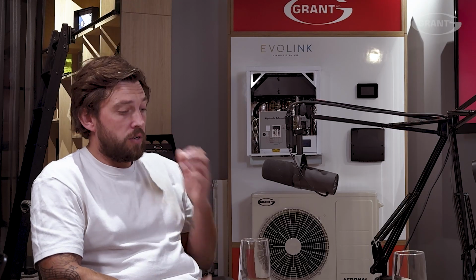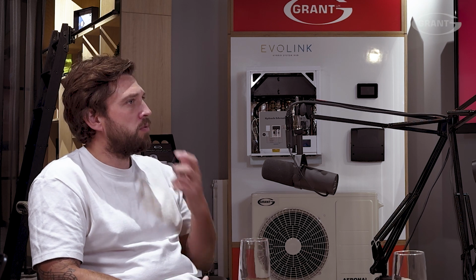Is that something that would be set during commissioning, or once you've gone, can you talk to a homeowner and get them to adjust it lower if they want to make it more efficient? Yes, so this is where remote access comes in, and I really like that. You can only set it up so much on commissioning. You might be fitting it in summer, and then you can't really commission it properly because of winter. So it might need a return visit, which I generally do after about 6 months if it's a summer install. Go back and have a visit in winter just to tweak things.